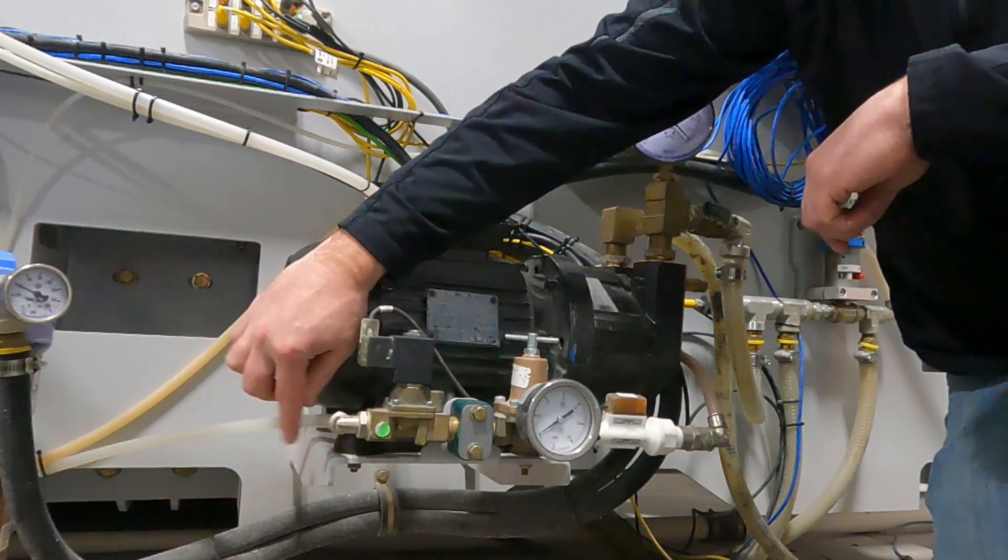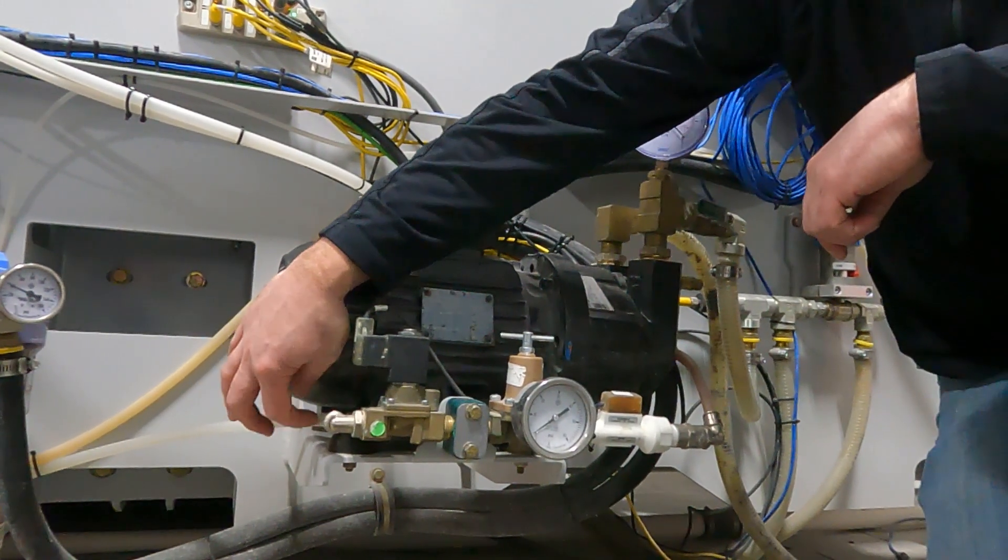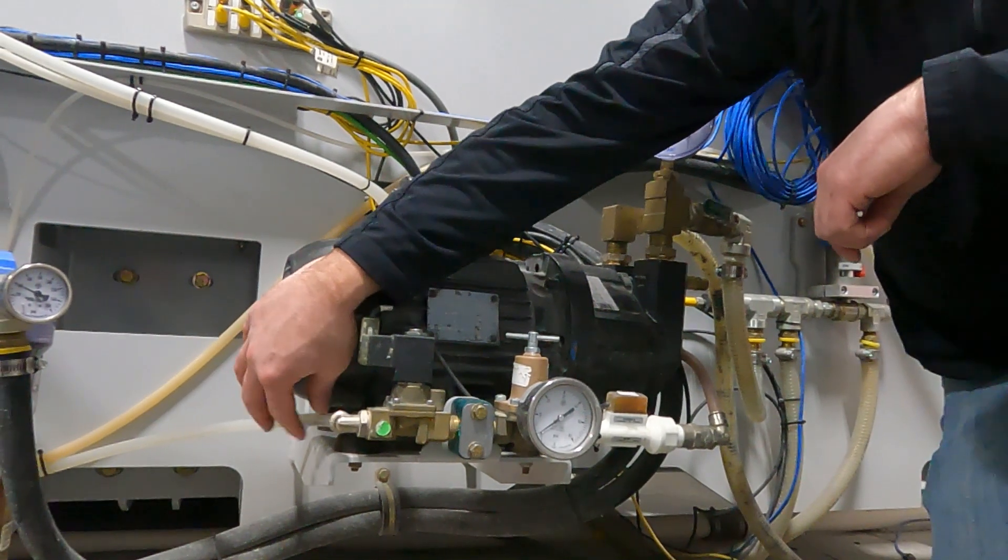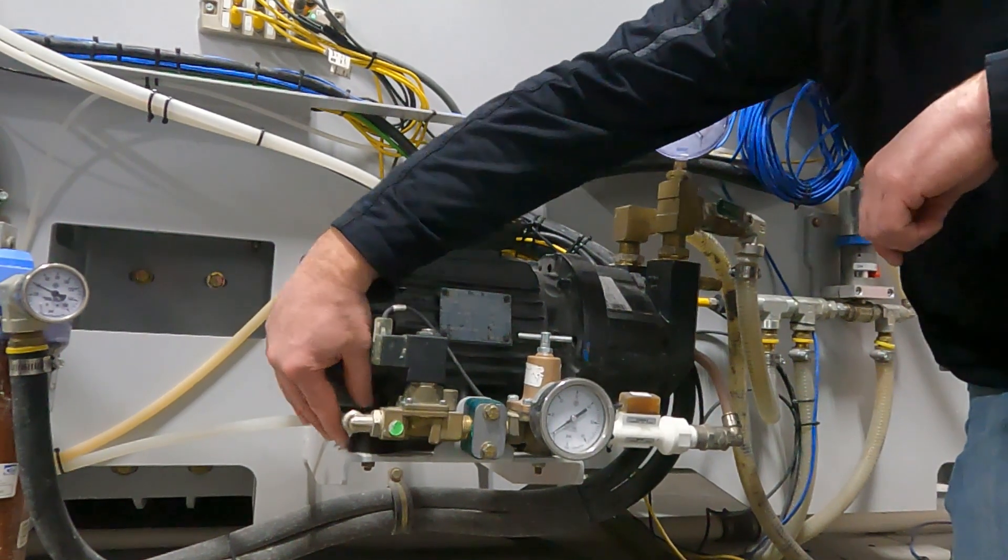If you want, you can take this off and make sure you have good water flow up to this point. And then you know your filter and Y strainer are good.